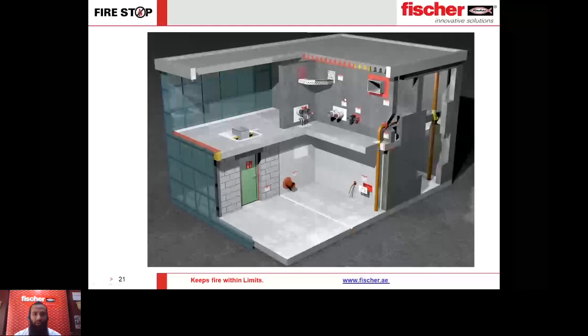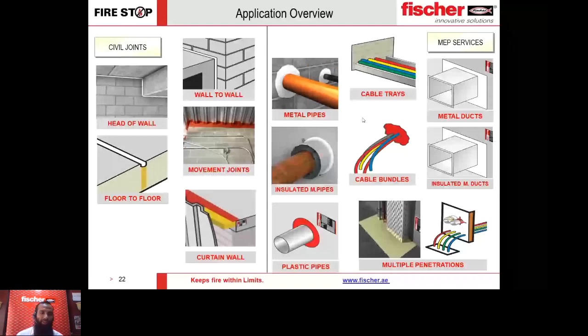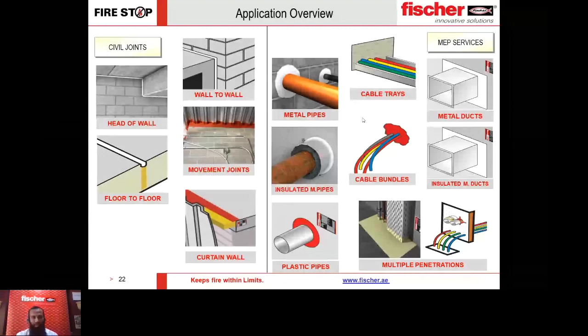Passive systems include fire stopping as well as fire doors — we need to seal around fire doors and around all penetrations. For ease of explanation I have divided applications into two main categories: number one, civil joints related to civil contractors; and number two, MEP services. For civil joints, the fire barrier is constructed up to a certain level of the slab leaving a small joint, plus there are joints between deck sheets, floor-to-floor construction joints, and expansion joints — all needing fire stopped treatment.